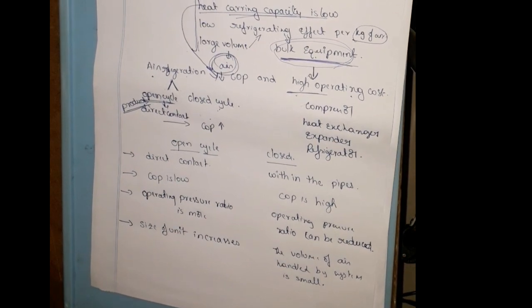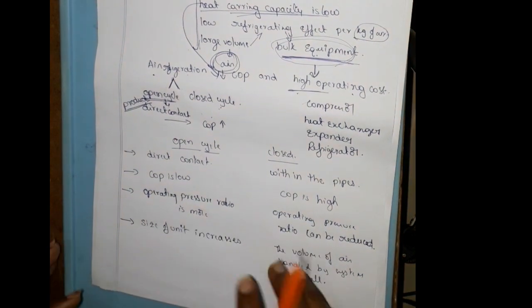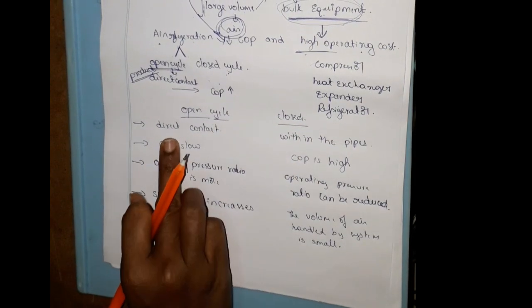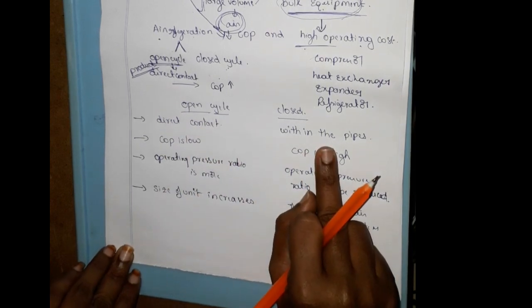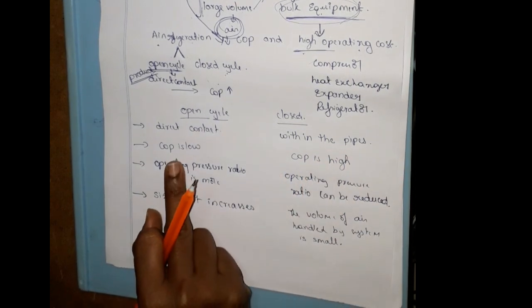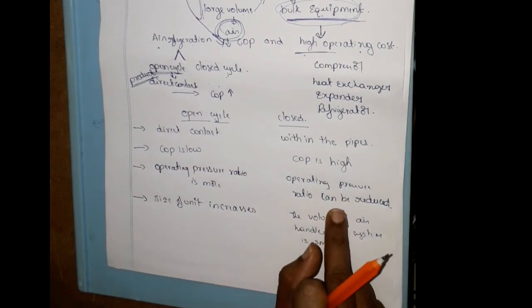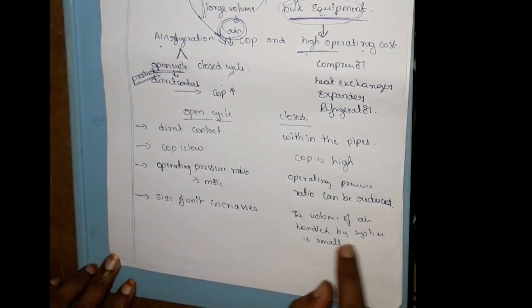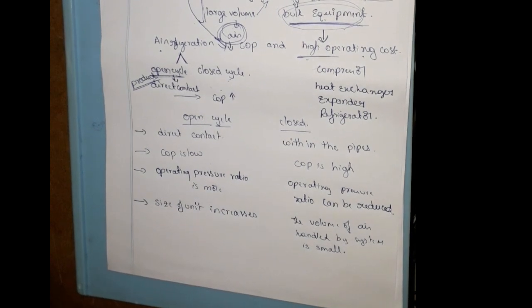The difference between the open and closed air refrigeration systems has four points. First: open cycle — direct contact; closed cycle — air circulated in pipes. Second: COP is low in open cycle, COP is high in closed cycle. Third: operating pressure ratio is more in open cycle, but can be reduced in closed cycle. Fourth: size of unit increases in open cycle, while the volume of air handled by the system is small in closed cycle.